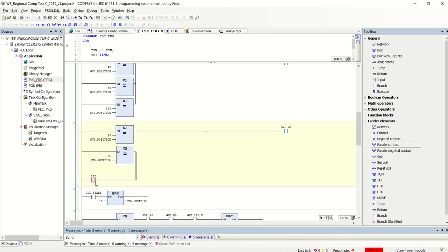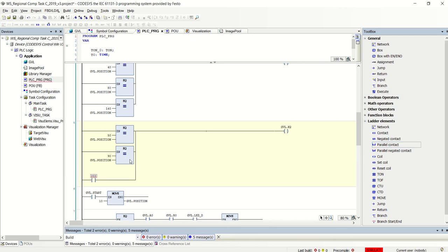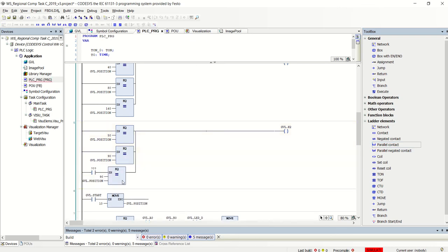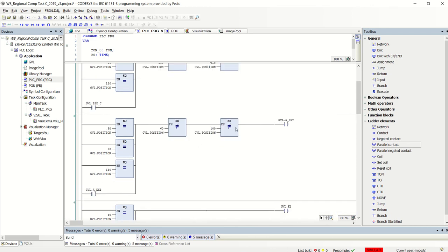Sorry, I need to tidy this up. Don't know why that's a parallel contact. And yeah, it should look like that. So 150, pop that in, delete him. Should bring him back. Remember, K2 will bring B back, and then we've got to break A at 150.